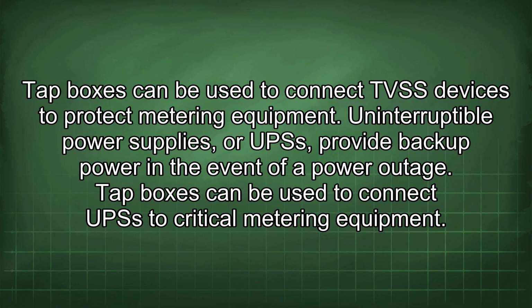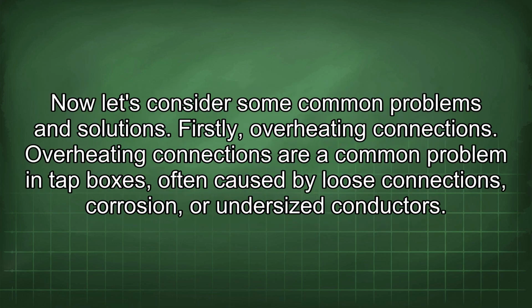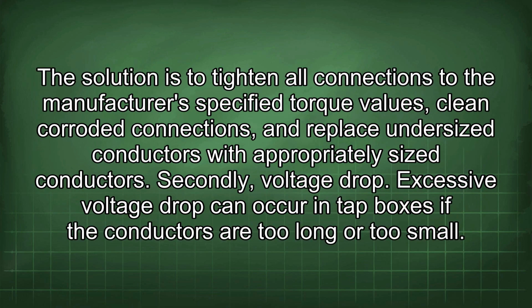Uninterruptible power supplies, or UPSs, provide backup power in the event of a power outage. Tap boxes can be used to connect UPSs to critical metering equipment. Now let's consider some common problems and solutions. Firstly, overheating connections. Overheating connections are a common problem in tap boxes, often caused by loose connections, corrosion, or undersized conductors. The solution is to tighten all connections to the manufacturer's specified torque values, clean corroded connections, and replace undersized conductors with appropriately sized conductors.